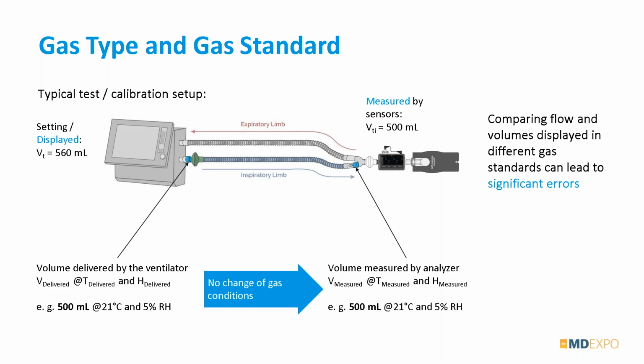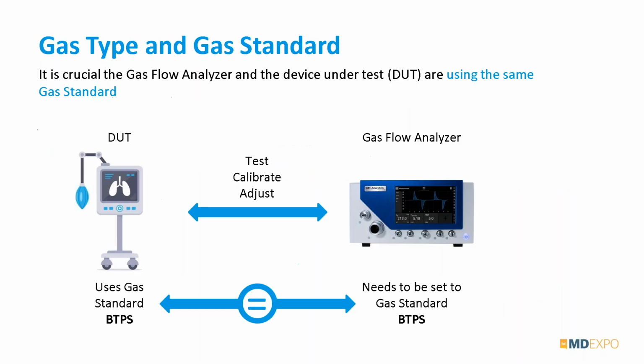So what can we do? Because now we're not comparing the same standard. We're basically comparing BTPS to ATP. Well, your analyzers have a setting called a gas standard, and you can select BTPS. As a matter of fact, whatever ventilator you're using, and not all of them do BTPS, some do ATP, STP, AP21, you want to make sure that whatever you're testing, you set your analyzer for.